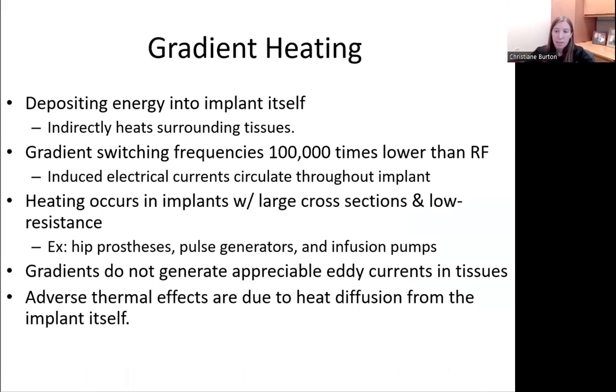Gradient-related heating is entirely different. The deposited energy within the implant itself indirectly heats surrounding tissues. Because gradient switching frequencies are 100,000 times lower than RF frequencies, induced electrical currents are not confined to the skin of the implant, but circulate throughout it. Heating may occur in implants with large cross-sections, having low resistance, closed current loops such as hip prosthesis, pulse generators, and infusion pumps. Gradients do not generate appreciable eddy currents in tissues, so any thermal effects are due to heat diffusion from the implant itself.